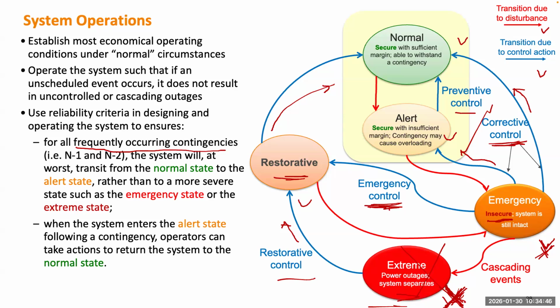Okay, for instance, the exciter, which can change the field voltage or field current of the generator, can participate in voltage control. So that voltage control can contribute to maybe the preventive control for some situations, and corrective control, and also emergency control. So it can contribute to many things, but some other controls focus on just one type of control.